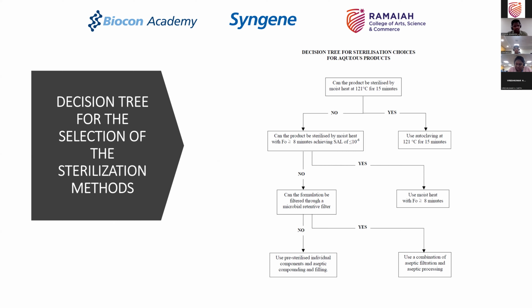If the answer is yes, then again change the condition of moist heat sterilization and go ahead with the sterilization process. So here, if you look at it, the first thing is the first condition, which is 121 degrees centigrade at 15 minutes. Again, please remember 121 degrees centigrade is using saturated steam. This condition could be slightly different based on the product.